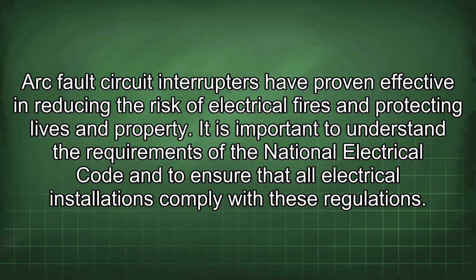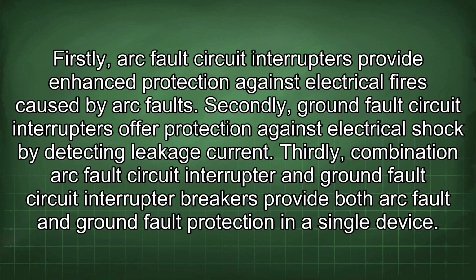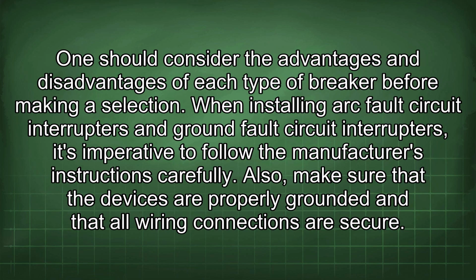Firstly, arc fault circuit interrupters provide enhanced protection against electrical fires caused by arc faults. Secondly, ground fault circuit interrupters offer protection against electrical shock by detecting leakage current. Thirdly, combination arc fault circuit interrupter and ground fault circuit interrupter breakers provide both arc fault and ground fault protection in a single device. One should consider the advantages and disadvantages of each type of breaker before making a selection.